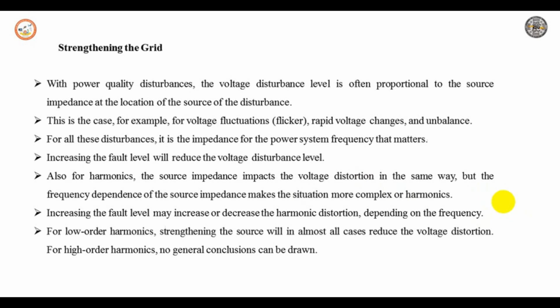With power quality disturbance, the voltage disturbance level is often proportional to the source impedance at the location of the source of disturbance. For example, voltage fluctuation or voltage flicker, rapid voltage change, and unbalance. For all these disturbances, it is the impedance at power system frequency that matters. Increasing the fault level will reduce the voltage disturbance level.